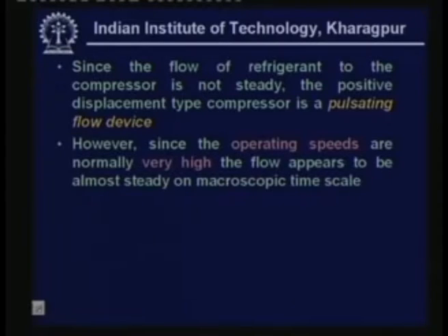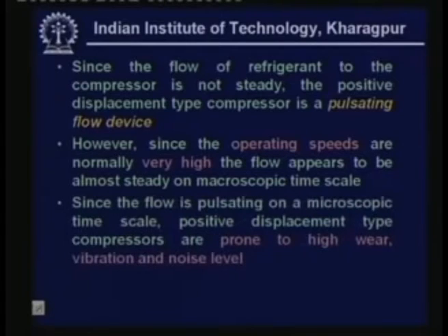However, since the operating speeds are normally very high, that means the rotational speeds of the compressors are so high, that the flow appears to be almost steady on a macroscopic time scale. However, since the flow is pulsating on a microscopic time scale, positive displacement type compressors are prone to high wear, vibration and noise level. So this is one problem with the positive displacement type compressors.